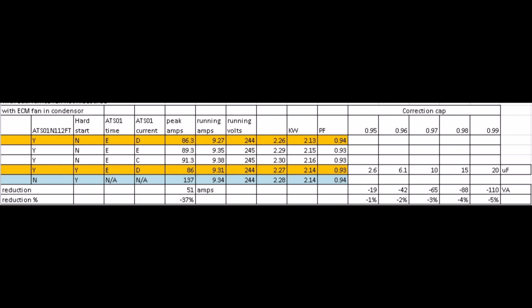The Magnum inverter can easily power the AC unit once it's up and running. It only needs 9 to 10 amps, just not when it can start. So I have come up with another plan, and I'm going to try it out, and maybe I'll use this soft start for a window air conditioner or a dehumidifier or something. The Magnum can provide a much larger surge current on 120 volt loads compared to 240 volt loads.